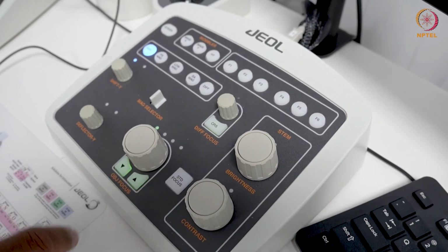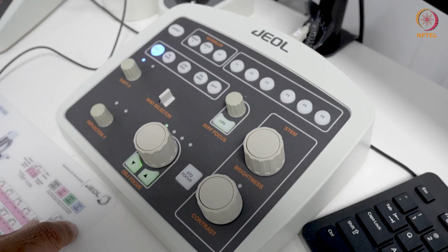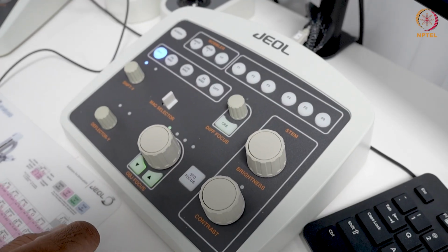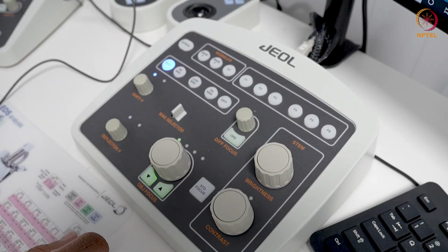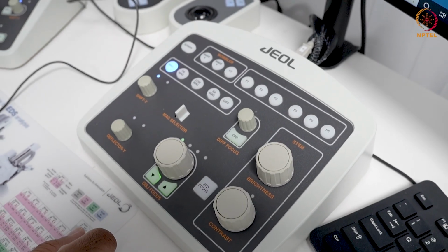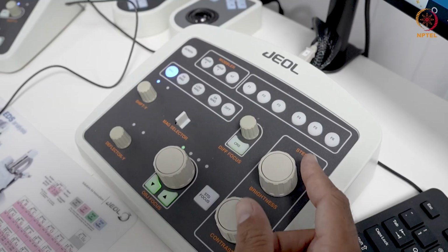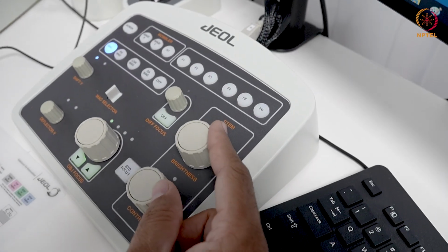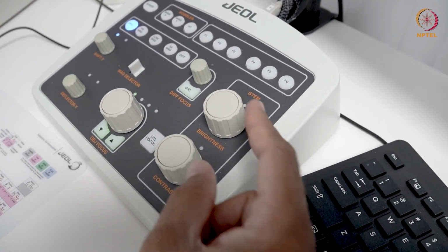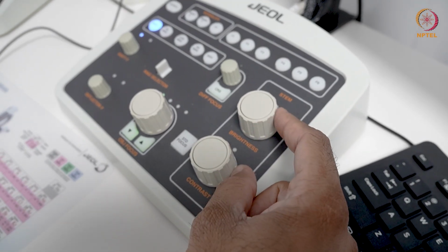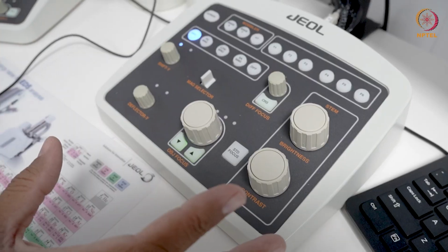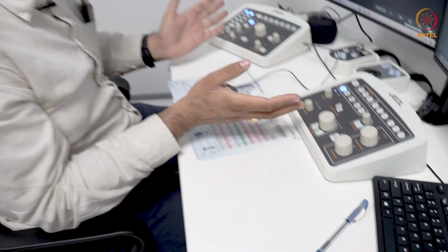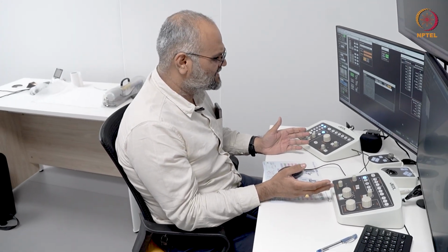The standard focus, once you load your saved alignment files, you typically press this to run a loop, and then you see that all the lens currents are at the standard preset values as per the previous working alignment. These two knobs here, when you're recording STEM images, you're scanning, and this is to set the brightness and the contrast of your STEM images.